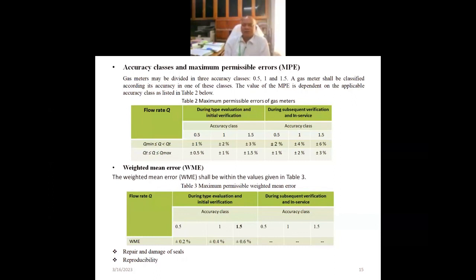And during the subsequent verification and in service, for accuracy class 0.5, the maximum permissible error is plus minus 2%, for accuracy class 1 plus minus 4%, and for accuracy class 1.5 this is plus minus 6%. So in service condition, the maximum permissible error is almost double the initial verification.